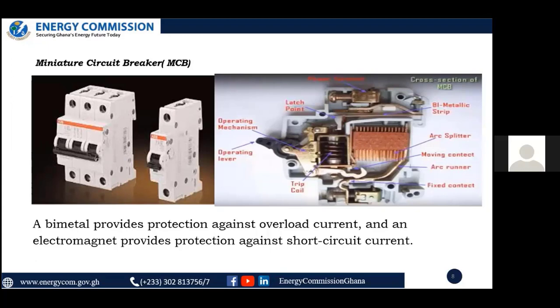The second mechanism on which the MCB operates is short circuit. A short circuit is simply saying your live and your neutral have merged. If your live and your neutral in the electrical installation merge, we call it a short circuit. When it happens, it generates a high current. This fault current causes the MCB to also trip. There's an electromagnetic mechanism also in the MCB. So you see one device is operating under two fault conditions, overload and short circuit. That's the advantage this MCB has over the fuse. You can reset it easily when the fault has been cleared. You don't need any technical know-how to go and rewire the fuse again.